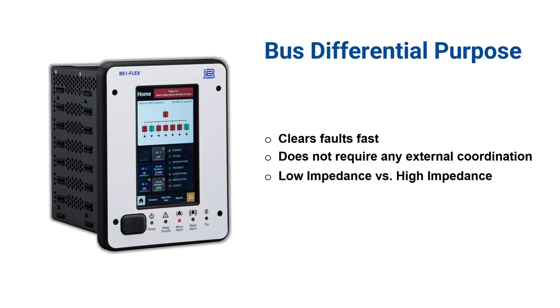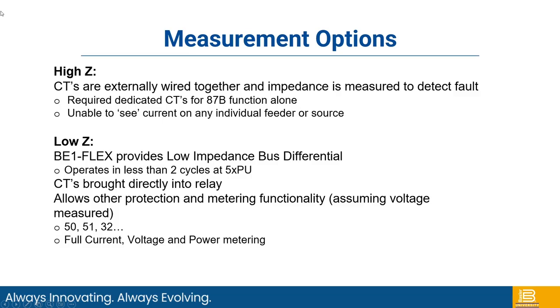So the next example is low impedance bus differential. It's used to clear faults quickly, and does not require any external coordination. There are two types, low impedance and high impedance. The BE1-FLEX uses low impedance protection. With high impedance, the CTs are externally wired together and impedance is measured to detect a fault. This requires dedicated CTs for the high impedance function, and it's unable to see the current on any individual feeder or source. So it's a little bit quicker, but they're both fast.